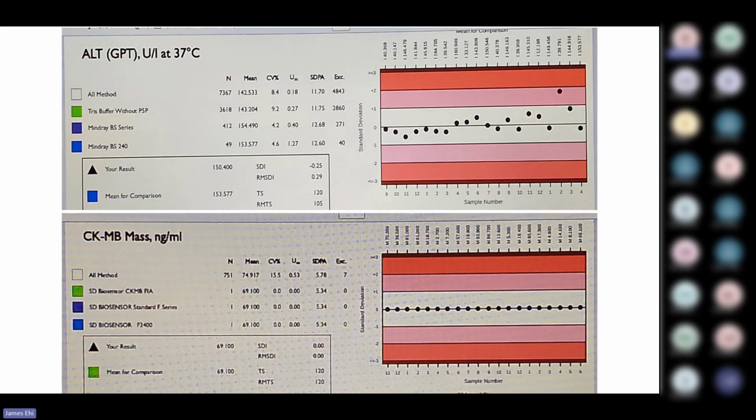But when you come here, you begin to see, look at the gap. Then it begins to drop. This is an example of poor precision. Your system is losing precision. That means you are drifting away from the acceptable quadrant of high precision to low precision. Your accuracy may still be there, but your precision is dropping.